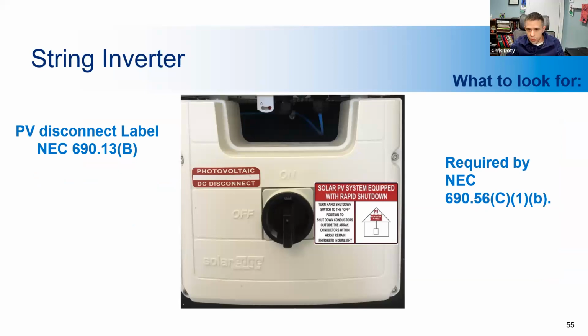Lastly, we're going to take a good look at it and verify the labeling requirements per NEC 690. This inverter has a disconnect handle built right into the inverter. It has to be labeled as a DC PV disconnect, and also that it has a rapid shutdown feature. And the labeling is super important for future maintenance. If an electrician has to work on your house or the PV system, you need this labeling to have them know exactly what's there and what kind of hazards are there. And it can also be useful for first responders.